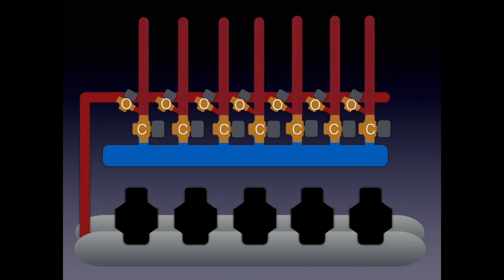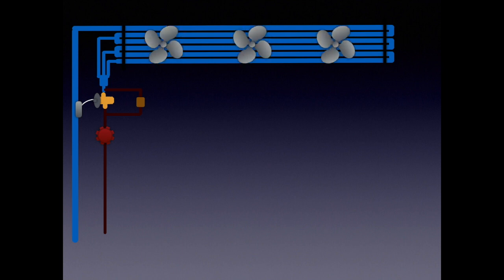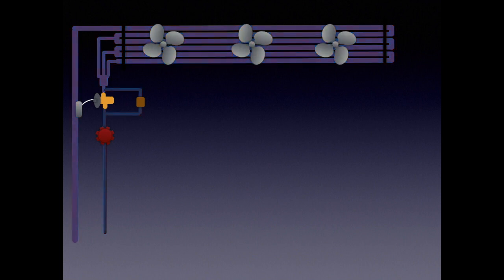And essentially this is what's going to happen. That hot gas is going to flow in the opposite direction that we just went over. Now your fans are going to continue to run. That refrigerant is coming back through the suction now. That hot vapor is traveling back through the suction. And at some point those fans are going to sense that temperature change and they're going to stop running. Because they don't want to blow hot air on your product.